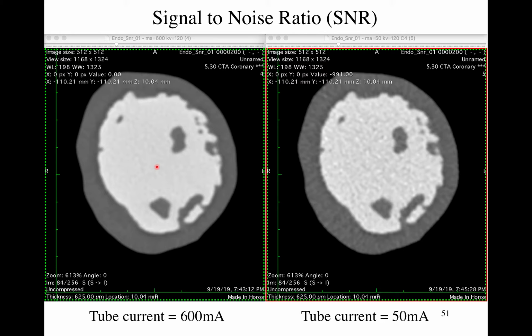For this acquisition, we set energy, etc., and we crank up the number of electrons hitting our tube to make X-rays to 600 milliamps. That is the current. The reason we pick 600 is that it's as high as you can go. That's as much as you can do. You can crank away, it's not going to give you any more, right? 50 mA is as low as you can put that current. And I'm not really sure of the confidence of when you ask for 50, it might give you 47, might give you 43, I don't know, it might get a little bit imprecise down there.